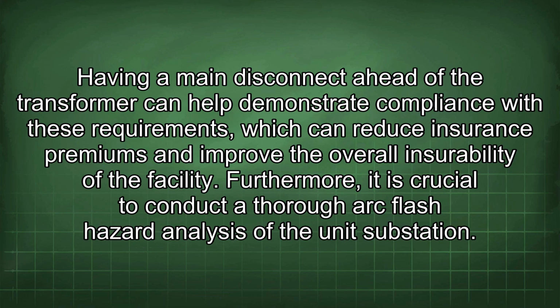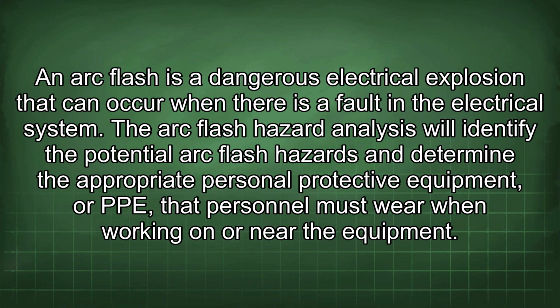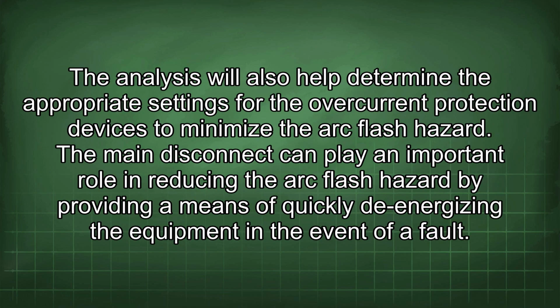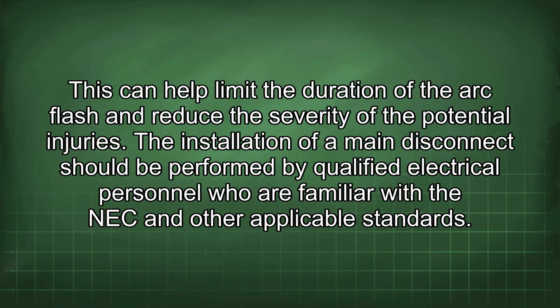Furthermore, it is crucial to conduct a thorough arc flash hazard analysis of the unit substation. An arc flash is a dangerous electrical explosion that can occur when there is a fault in the electrical system. The arc flash hazard analysis will identify the potential arc flash hazards and determine the appropriate personal protective equipment, or PPE, that personnel must wear when working on or near the equipment. The analysis will also help determine the appropriate settings for the overcurrent protection devices to minimize the arc flash hazard. The main disconnect can play an important role in reducing the arc flash hazard by providing a means of quickly de-energizing the equipment in the event of a fault. This can help limit the duration of the arc flash and reduce the severity of the potential injuries.